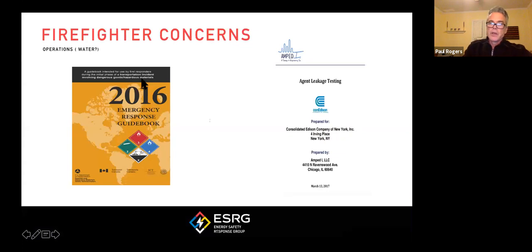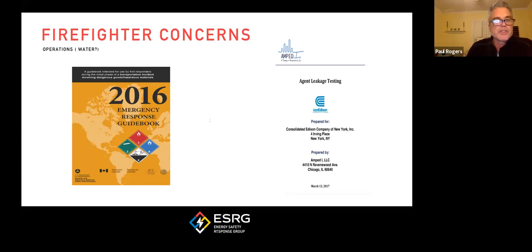Another concern we had is, can we use water on these things? If you take a look at the 2016 ERG - I haven't looked at the 2020, forgive me - when I first looked it up I went to the emergency response guide. This book is in every emergency vehicle, police, fire, and EMS, and it's a guide toward any hazardous material. Sure enough, lithium ion batteries are in there, and they give you guidelines on what you should do in the event of a failure of a lithium ion battery or ammonia leak or whatever. But what they tell you in this book is not to use water. So we were like, oh wow, what are we going to put this out with?